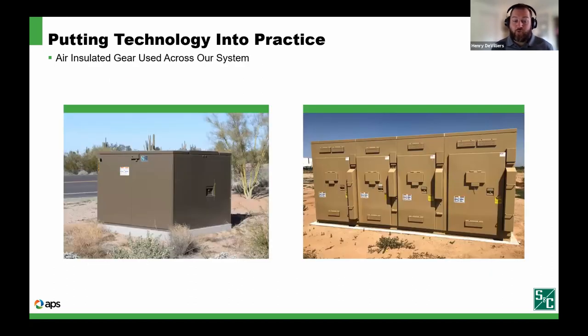When it comes to selecting the types of insulation that we use in our system, most of our system is handled by air insulated. As Joe mentioned, it's more cost effective. And being mostly in the desert, we have relatively low humidity most of the time, and the air insulated works great for us. That comes in the form of dead front switching cabinets, as well as live front when we use the metal enclosed switchgear, where we have zero lot lines and a lot less real estate to work with.